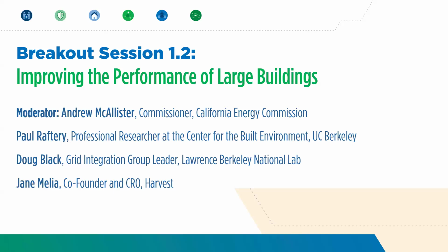But the good part is, if you just want to partially electrify, working within the existing constraints of your space or electrical capacity while retaining the existing gas boilers, you can get the vast majority of your loads electrified with a very small heat pump, because you don't need most of that capacity all year round. You only need peak capacity on the coldest day of the year. The vast majority of the time you need like 10% of capacity, so you can serve most of the annual energy consumption with a very small heat pump.